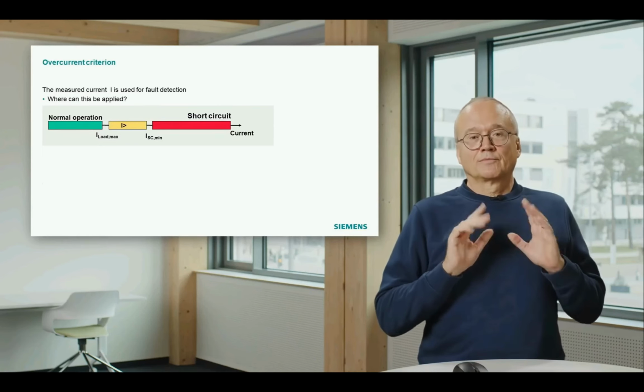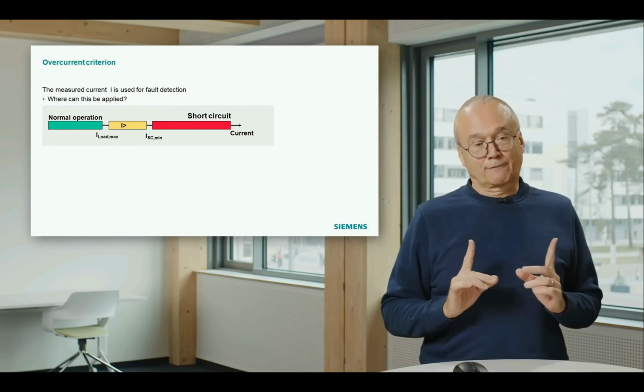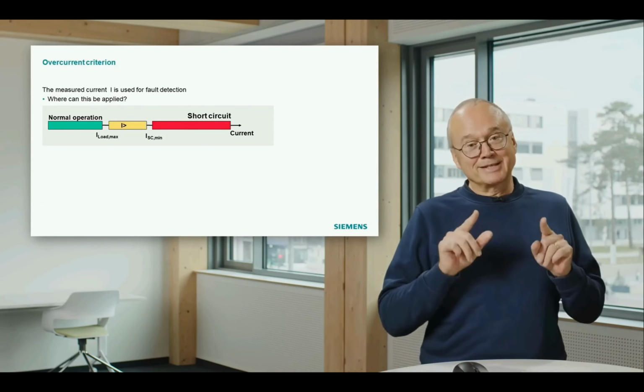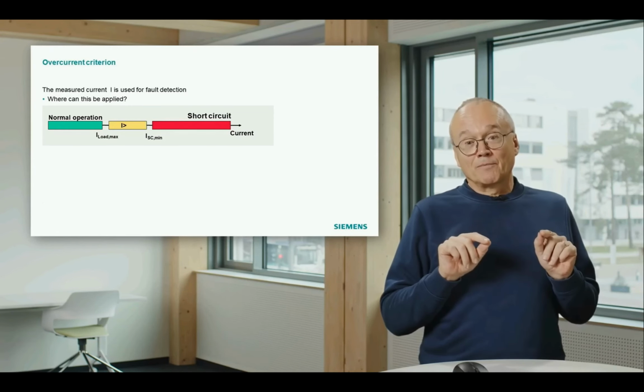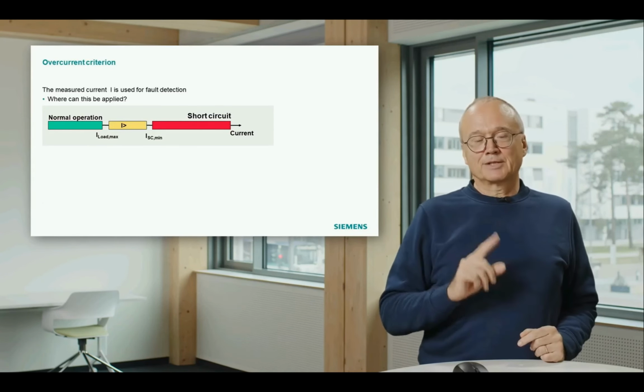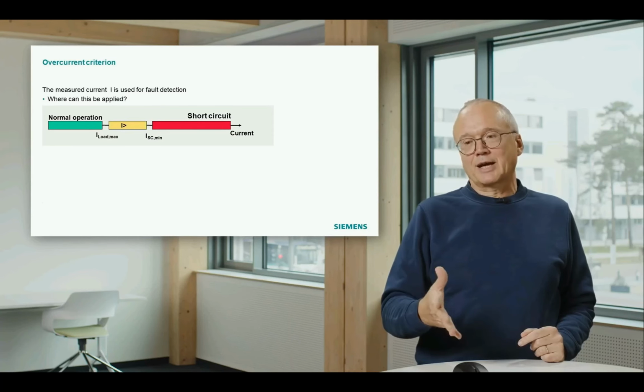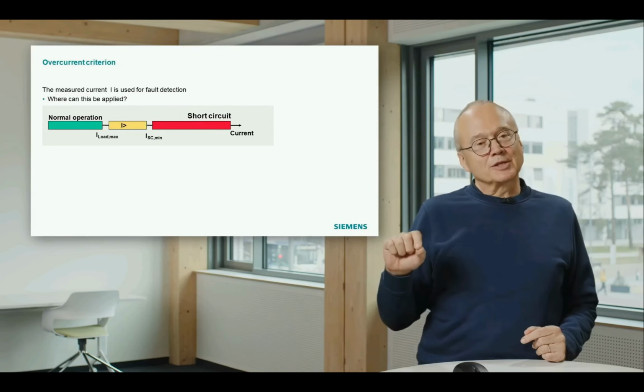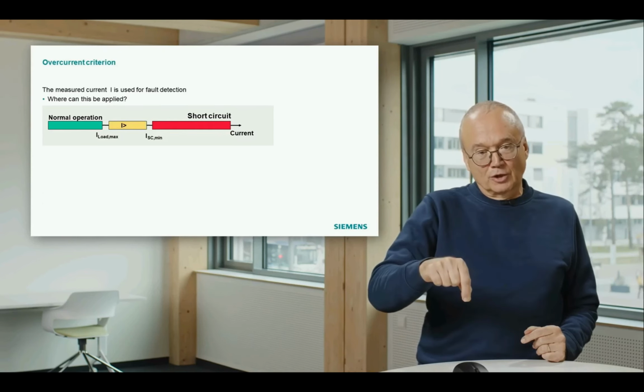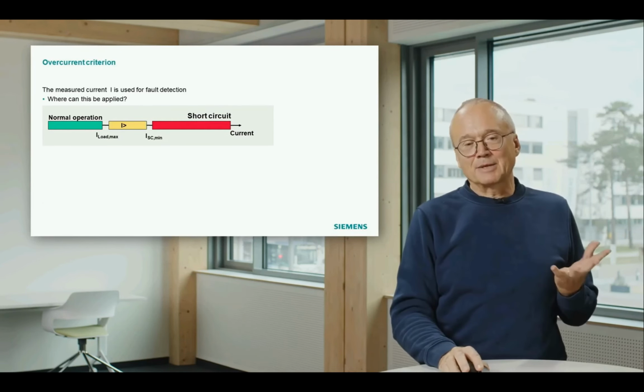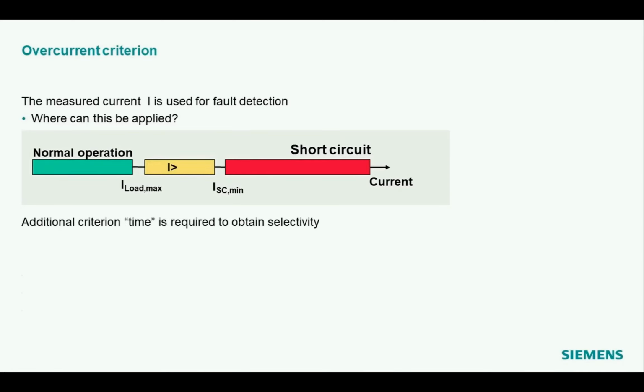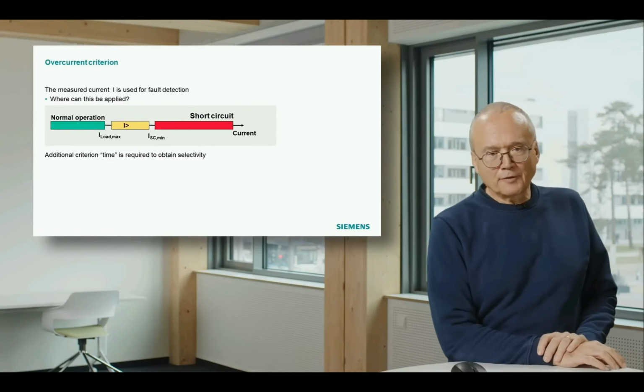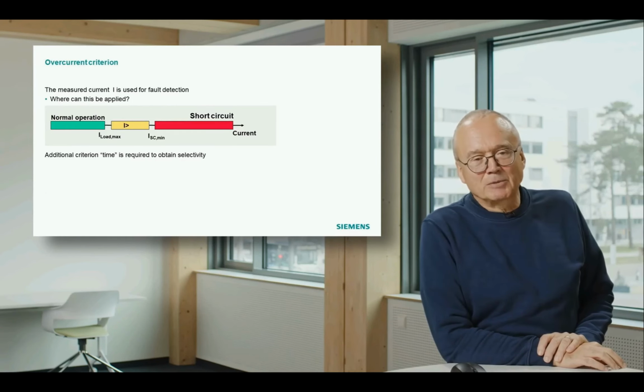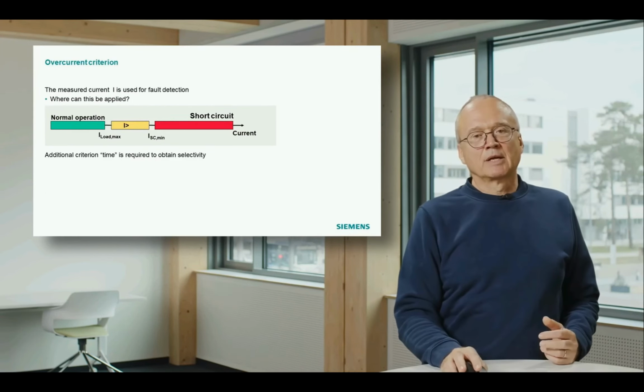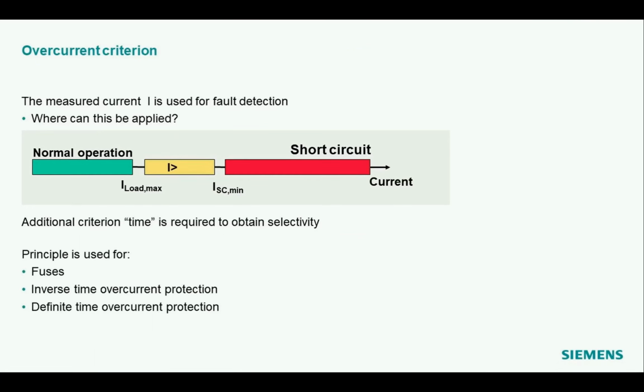That means if that can be applied, we can detect a fault. But remember, detection of a fault is one story. We also have to be selective. Detection of faults means the current is that high, there must be a short circuit, but we still do not yet have the decision: is the short circuit on our own line or is it on the next line? That means the topic of selectivity is not included here. We will see later on in the second part of this webinar that we need some time delays to get selectivity. But basically, this principle is widely applied.